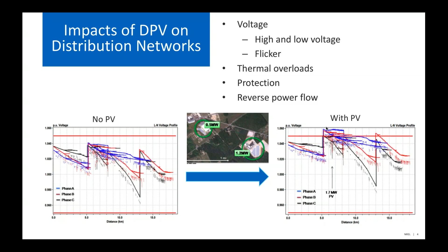So here's an example that I'm showing for a publicly available feeder from EPRI called the J1 feeder, and it's in the northeastern United States. You can see the profile for the voltage on the left when there's no PV present, and then after they had two large PV systems connected to the distribution network, they saw the voltage pushed up outside of the ANSI limits and observed an overvoltage violation on the system that they needed to mitigate.